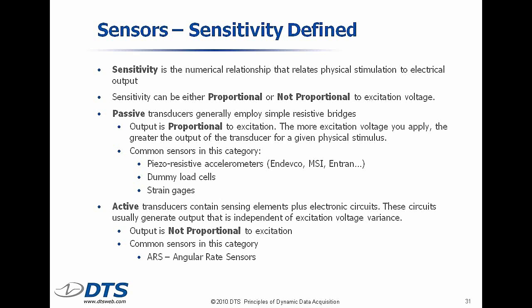Sensitivity in transducers can be either what we call proportional or not proportional to excitation. Passive transducers, like all of the Wheatstone bridges, that includes load cells, accelerometers, moment, force and moment gauges, are all what we call passive. They have no electronics, and their output is proportional to their input voltage, and we call that proportional. So you can see piezo-resistive accelerometers from Endevco, MSI, and Entran pretty much are all passive. Dummy load cells are passive. Strain gauges themselves are passive.